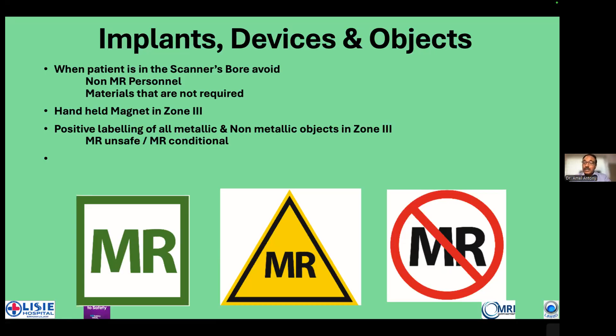Now coming to implants, devices, and objects. When the patient is in the scanner's bore, always avoid non-MR personnel being there, and always a handheld magnet in zone 3 can ensure that none of these objects are carried into zone 3 and zone 4. And anything which is along with the patient should be labeled as either MR safe, that is a green signal, MR conditional, that is yellow, and MR unsafe, that means it's completely not allowed to be taken into the MRI room. So these are some of the signages which can be there.